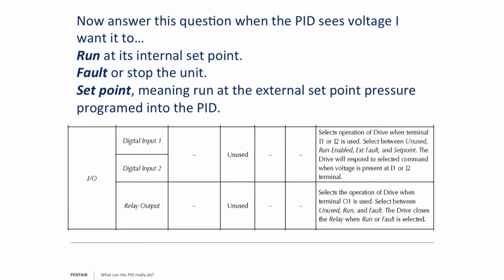Good example of this might be a float switch. So now what we need to answer the question is that when the PID sees this current, when it sees the signal, what do we actually want it to do? So we showed you the circuit, how we have it programmed. Let's say it's a float switch. If it's a normally open float switch, it won't pass current. So often what we recommend is if you want a run command, you want that to be a normally open float switch. So as the float rises with the water, say in the cistern, it gets to a fill point and the point snaps shut and applies voltage, telling the unit it's safe to run.